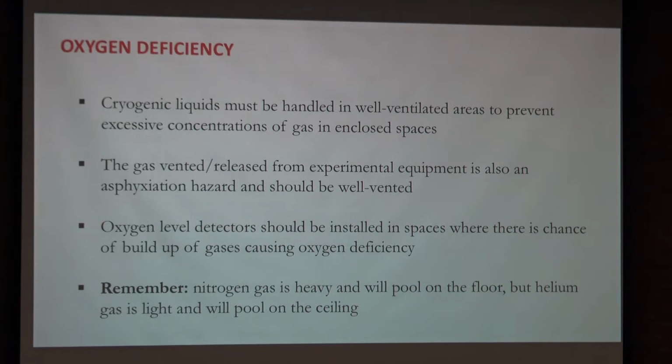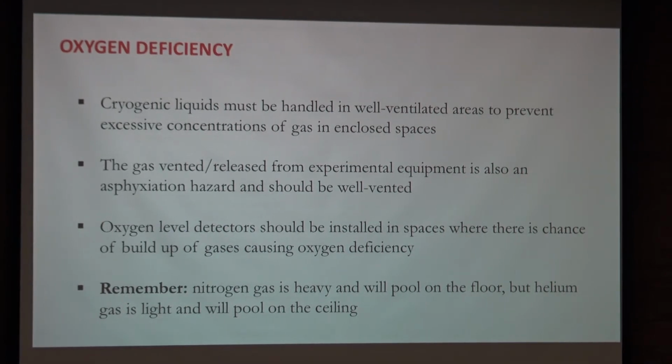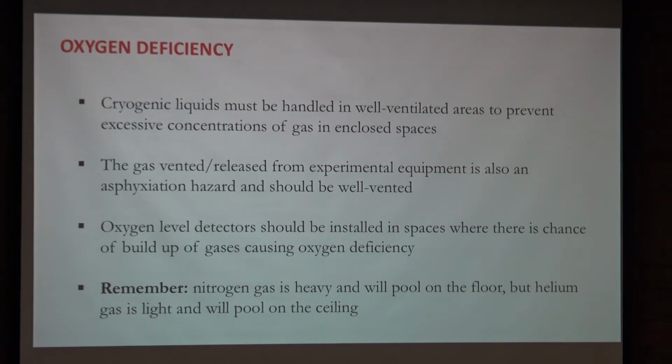When there is a place where you think there is a chance that oxygen deficiency can happen, you may want to think about installing oxygen level detectors. One thing to keep in mind: liquid nitrogen, one of the most common cryogenic liquids, is heavier than air, so it will accumulate close to the floor.